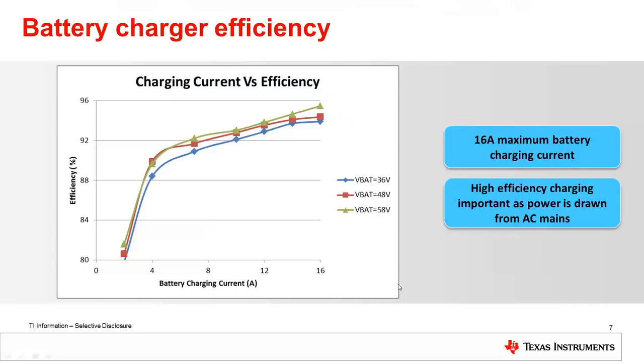In the battery charging mode, the max charging current is limited to 16 amperes by the firmware. It can be seen that the efficiency at full load when the battery is at its nominal voltage of 48 volt is as high as 94%, and it goes up to 95.5% when the battery voltage reaches its peak value of 58 volts. The high efficiency achieved during the charging mode is important as it reduces the power drawn from the AC mains.